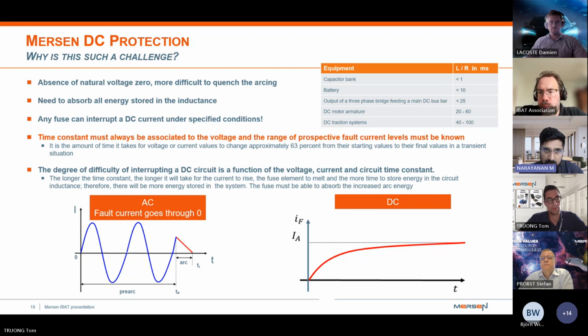That's why Mersen specializes in DC protection, providing safety for these systems. When we talk about DC, the important factor is the time constant - the ratio between inductance and resistance in the circuit. The associated voltage and range of prospective currents that the fuse has to open for must be really understood, and the right fuse implemented in the circuit. This is of specific importance when it comes to DC.